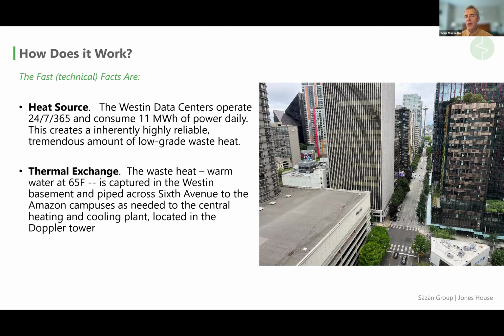If you're an engineer designing systems, let's say you're putting a boiler in a building to heat the people and make them comfortable, there's a certain reliability you can expect, and you can expect failures and things like that. One of the things that was really interesting here is I don't think I could come up with a more highly reliable source of low-grade waste heat than coming out of a data center, which, because of its function, is inherently highly reliable. It's got backup power, backup systems everywhere. Having that data center down for any amount of time costs money.